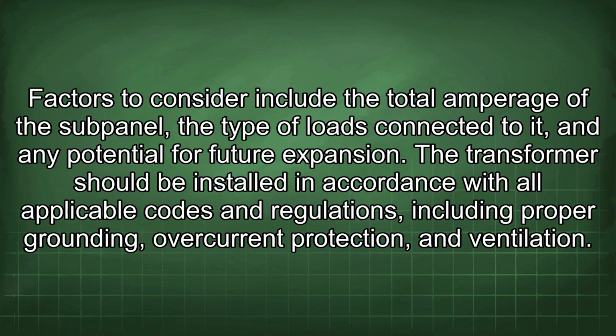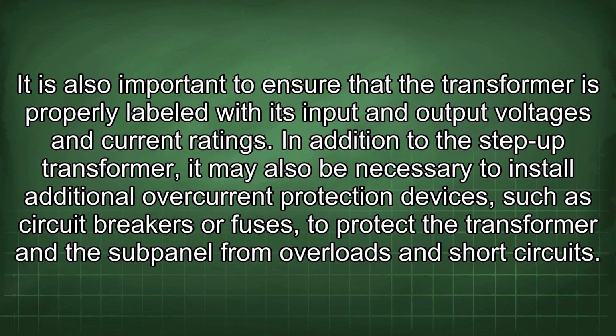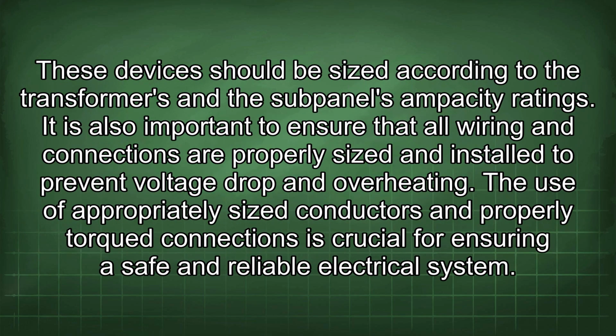Factors to consider include the total amperage of the subpanel, the type of loads connected to it, and any potential for future expansion. The transformer should be installed in accordance with all applicable codes and regulations, including proper grounding, overcurrent protection, and ventilation. It is also important to ensure that the transformer is properly labeled with its input and output voltages and current ratings. In addition to the step-up transformer, it may also be necessary to install additional overcurrent protection devices, such as circuit breakers or fuses, to protect the transformer and the subpanel from overloads and short circuits. These devices should be sized according to the transformer's and the subpanel's ampacity ratings.